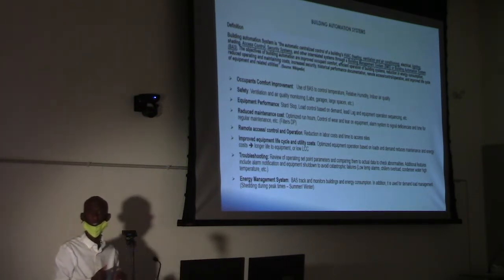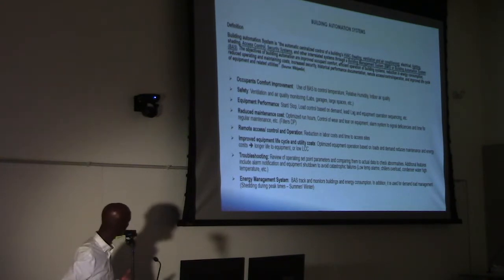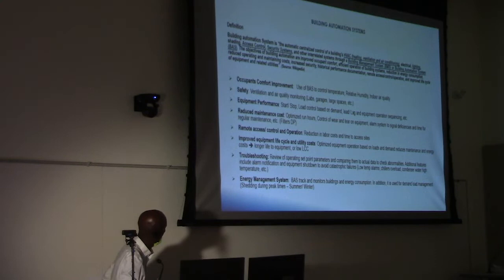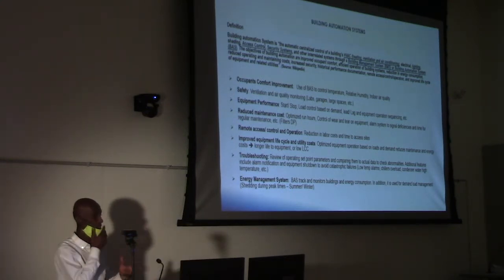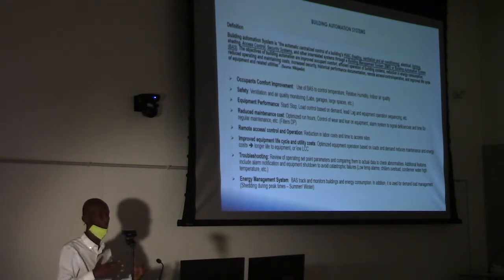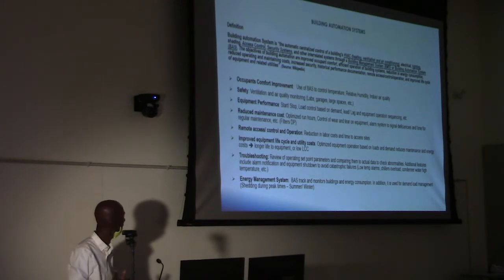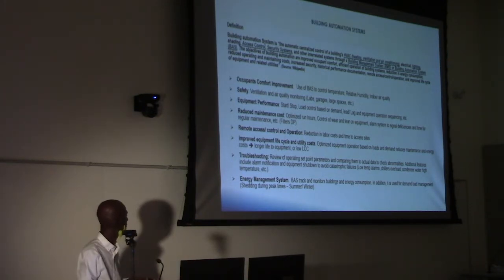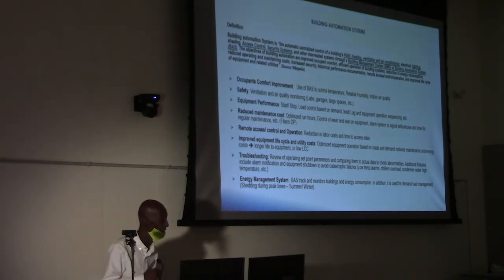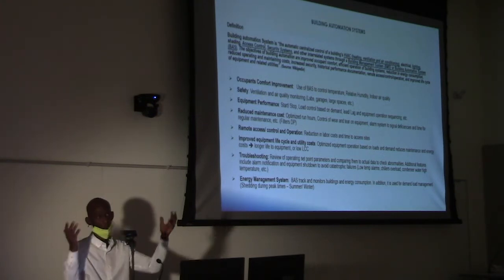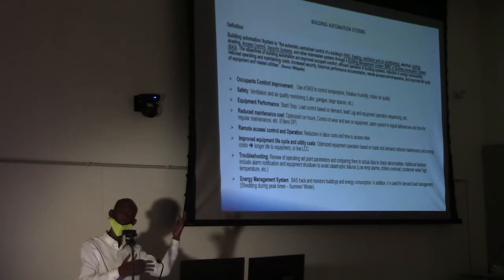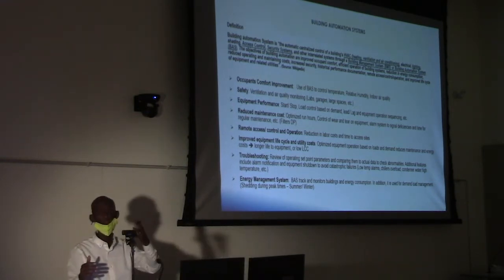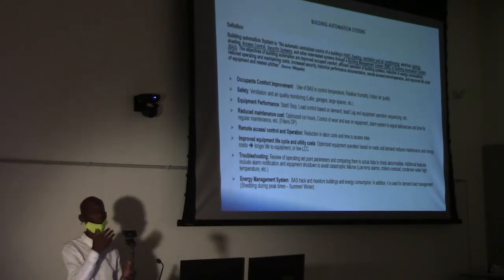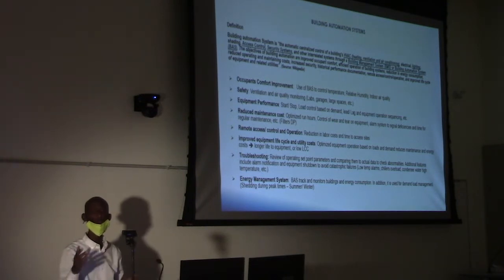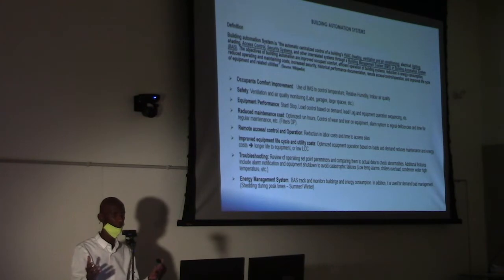Troubleshooting. I'll show you how we use the system on troubleshooting the equipment. Mostly, we have an alarm system that allows us to get notification when an equipment is not running properly or when it's failed. And also, we have a built-in system so that the equipment can shut down to avoid catastrophic failures. For instance, if it's, let's say, minus 20 degrees, and you open a damper of an air handling unit, and you have cold air running through a coil, and that coil doesn't have enough hot water to run through, guess what? That coil may freeze. If it freezes, it bursts. When it bursts, guess what? You have a flooding. You have a major issue.